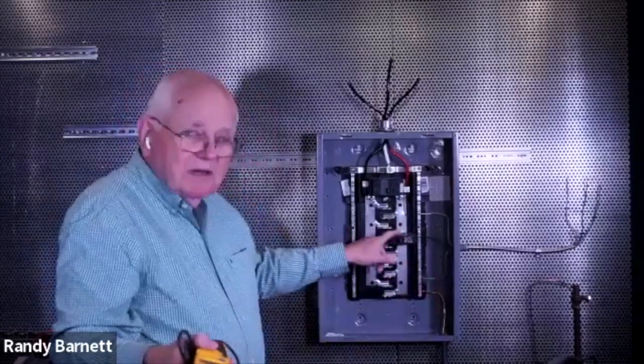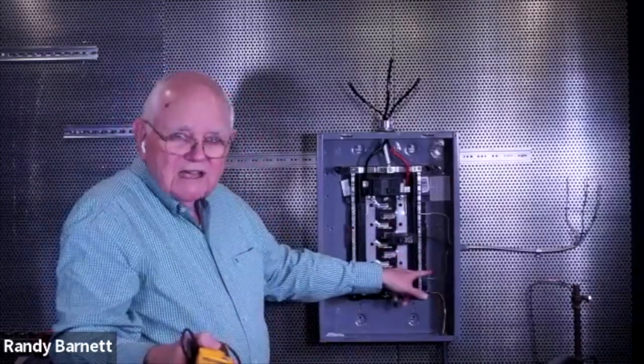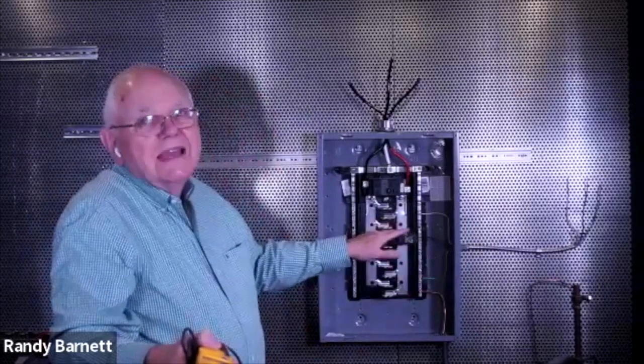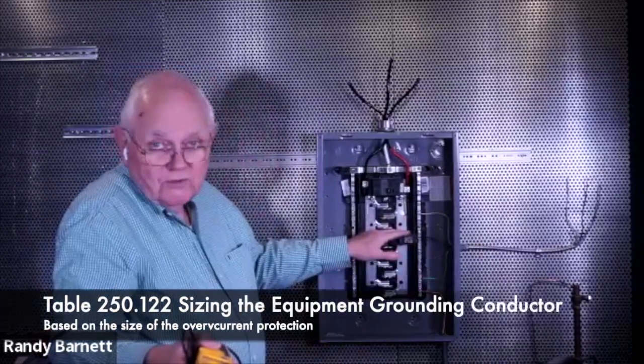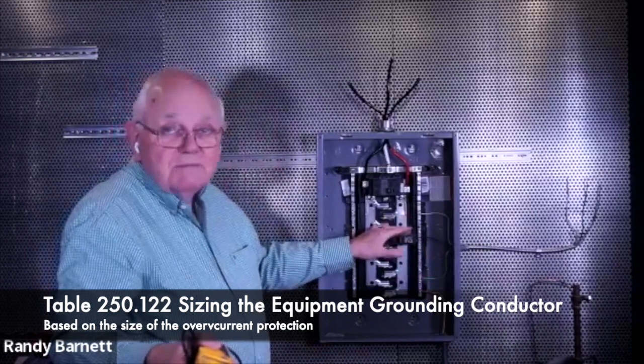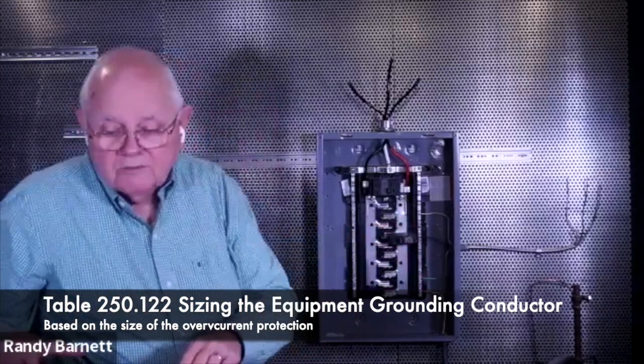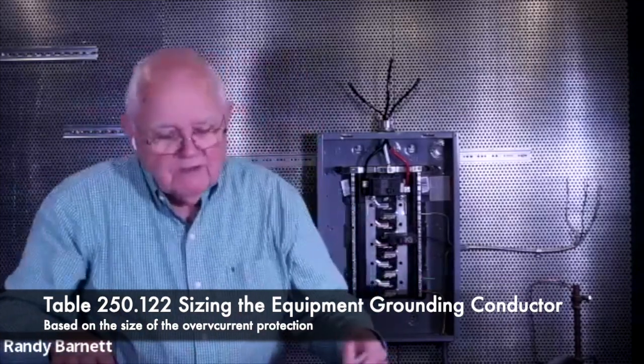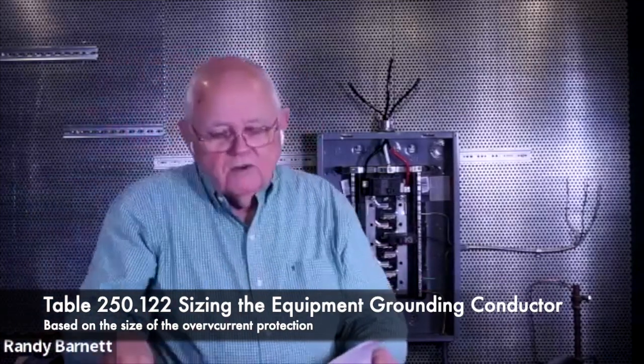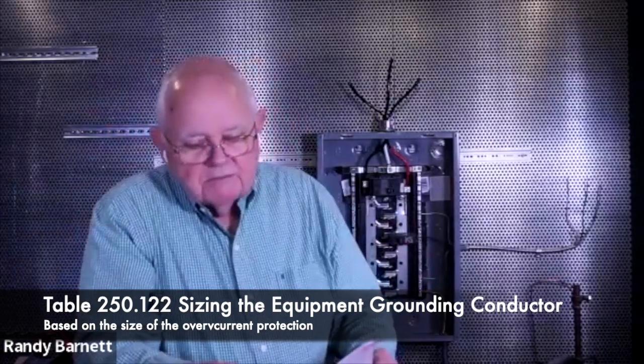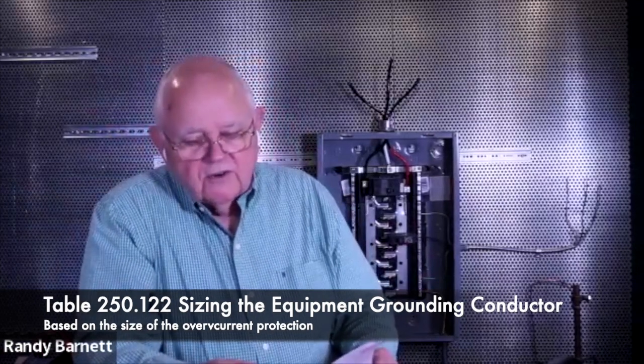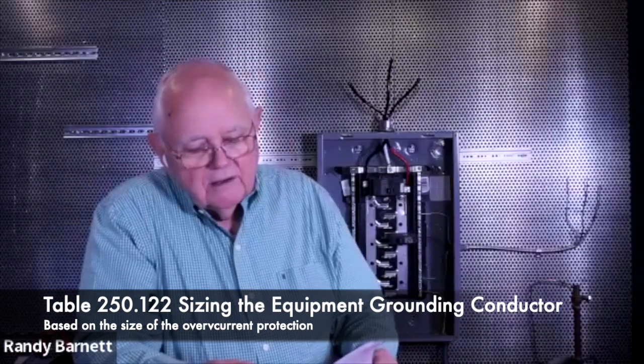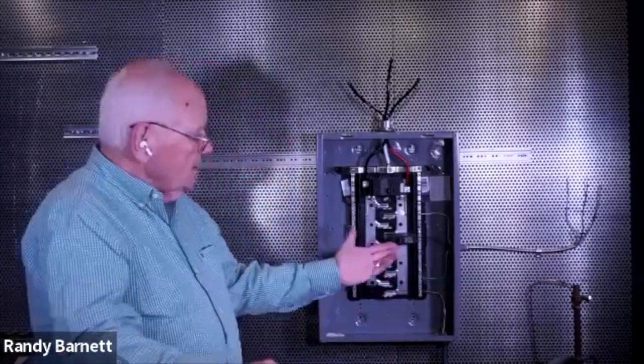Well, let's see. It's protected by the circuit breaker. So why don't we size the equipment grounding conductor based on table 250.122, which is based on the size of the overcurrent protection. For instance, we go to table 250.122, and it says minimum size equipment grounding conductors for grounding raceway and equipment. For a 15 amp circuit breaker, which is what this is, it says that the copper 14 would be my minimum size equipment grounding conductor.